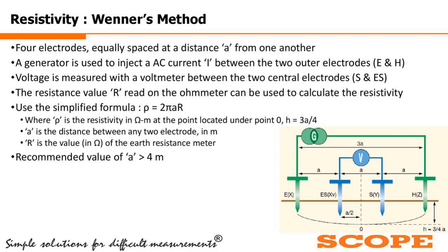And as we can see in the picture, the distance between all four earth probes, or the earth electrodes, has to be kept constant. So the four electrodes are equally spaced at a distance a from one another. They should be placed at an equal distance.